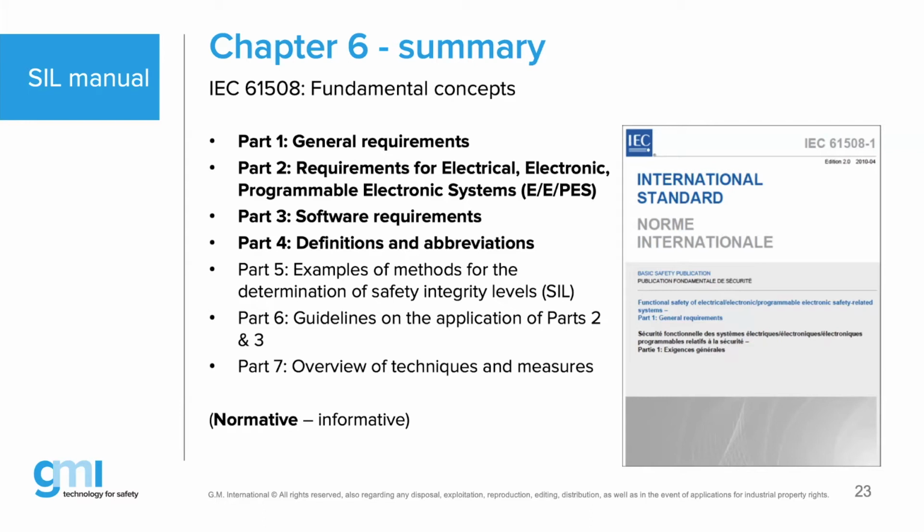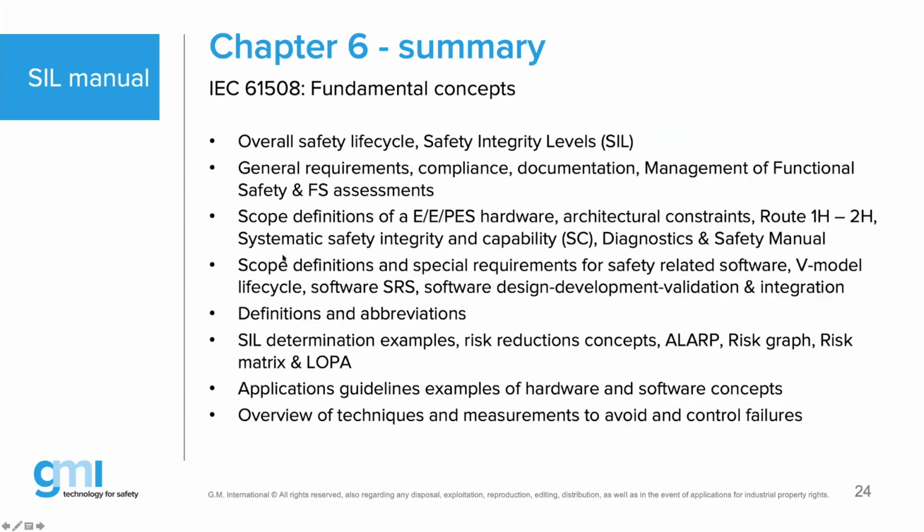And Paolo mentioned in the company introduction that they are SC3 compliant. That means the GMI company had to prove that the quality and the rigorousness of their design of hardware and software is to part 7 of the 61508. And when they fulfill the column for SIL 3, then they get the certification mentioning SC3, and that's based on part number 7. As you can see, part 5, 6, 7 is informative, but part 1, 2, 3, 4 is normative.